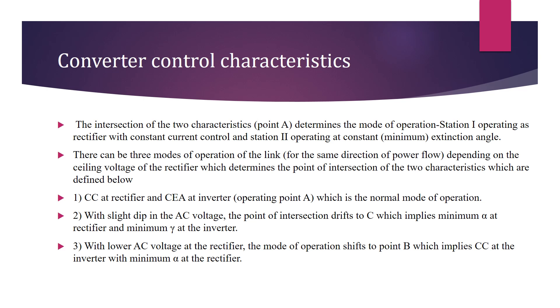The second mode: with a slight dip in AC voltage, the point of intersection drifts to C, which implies minimum alpha at rectifier and minimum gamma at inverter. Alpha is the firing angle and gamma is the extinction angle. With lower AC voltage, the mode of operation shifts to point B, which implies constant current at the inverter.